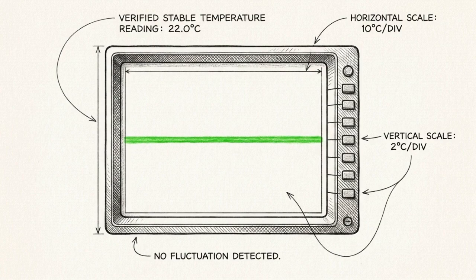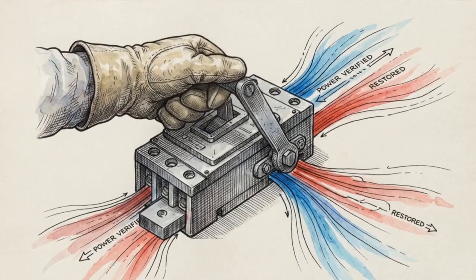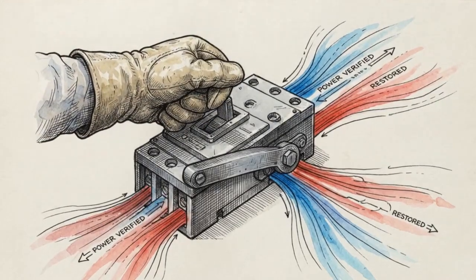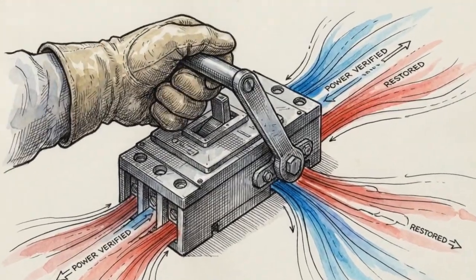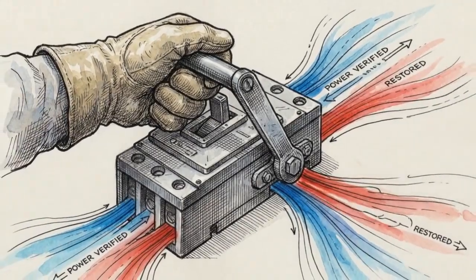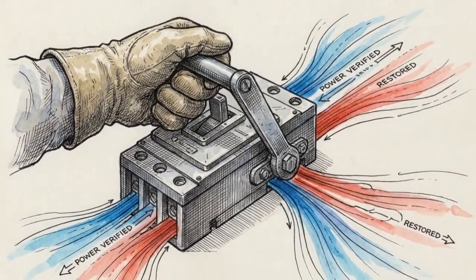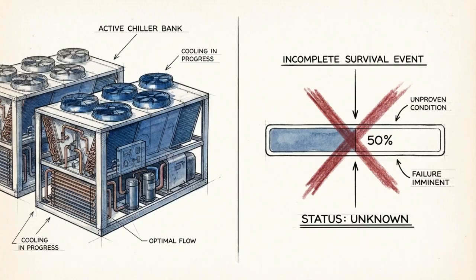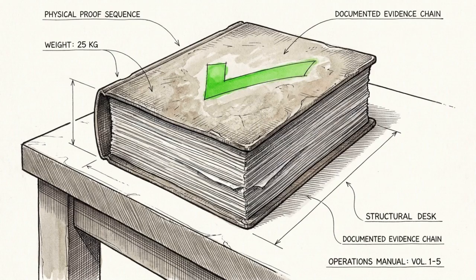The system only returns to the ready state when the tank reaches full capacity, all alarms are reset, and automatic control authority is successfully reproven. Ultimately, a survival event is not finished when the chillers turn back on. It is only over when the complete evidence chain is indexed and the system is safely restored to a physically proven ready state.